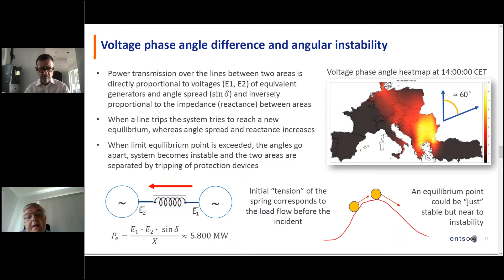And so luckily they did it, and they will always do it, and they will continue to do it, and we will never take these protections out, because this is exactly what you have to do. As soon as the system starts oscillating, you have to split it. This is the only way to create again a stable system, and indeed, immediately after the split, both systems became stable again almost immediately. Voilà. So here you see some graphs of exactly what happened, and the phase angle graph is quite impressive, of course, where you see that the system is completely unstable.